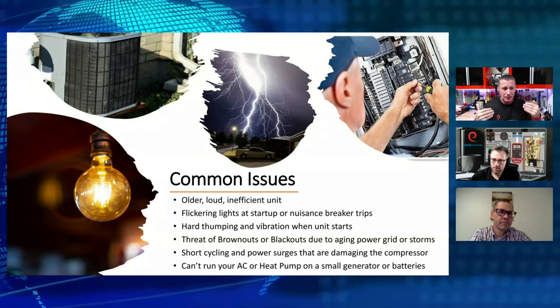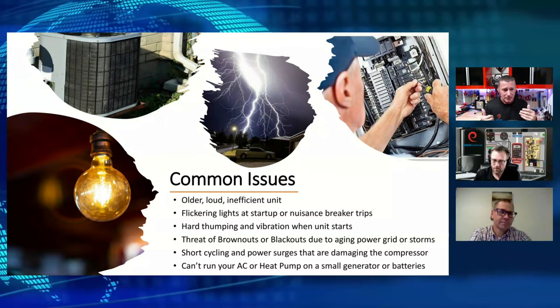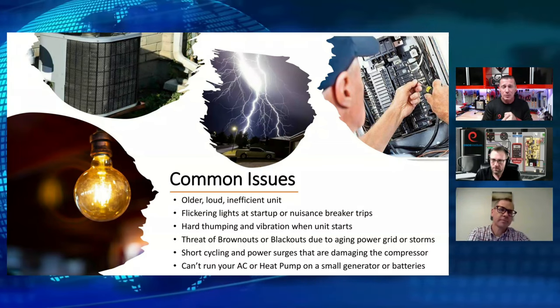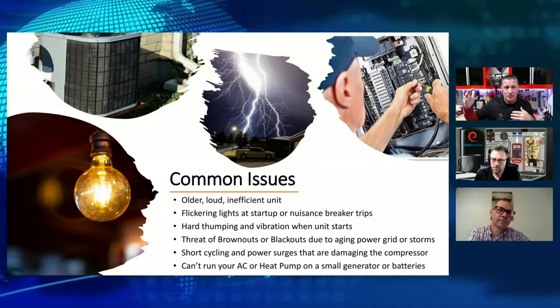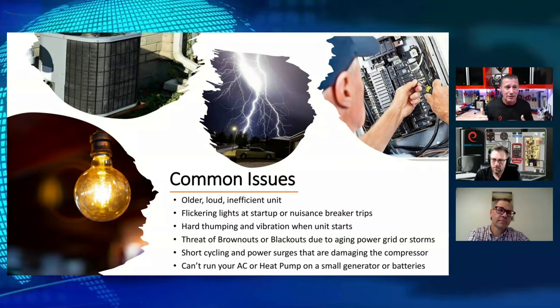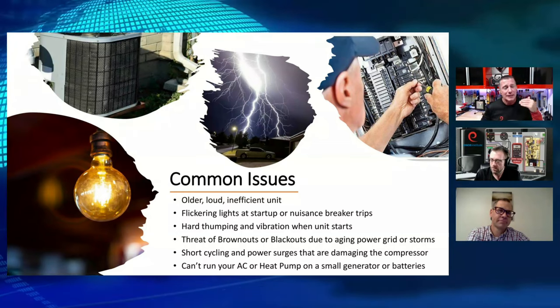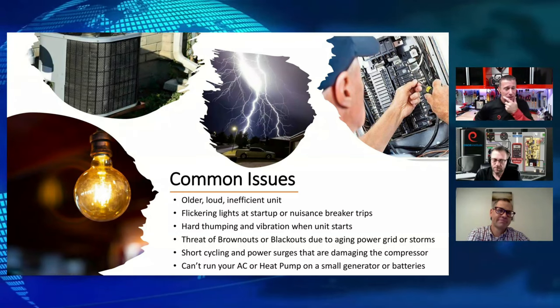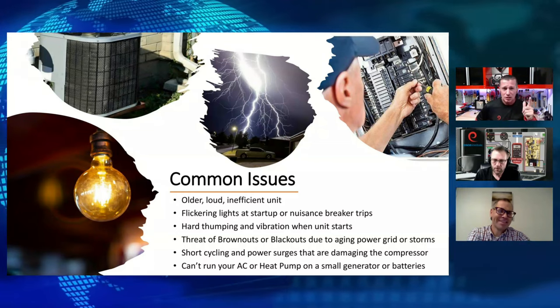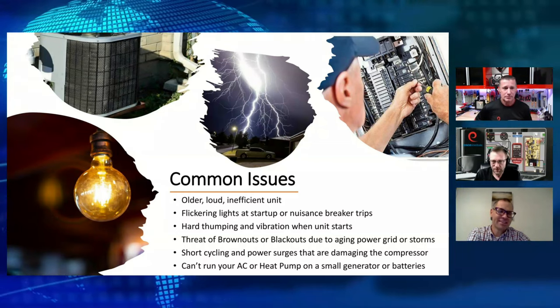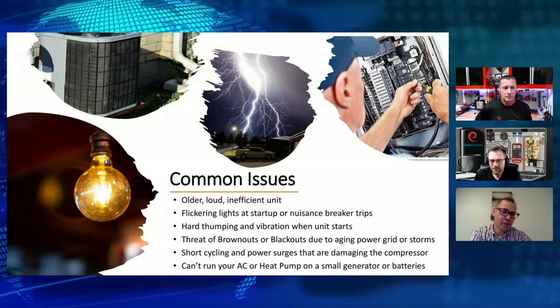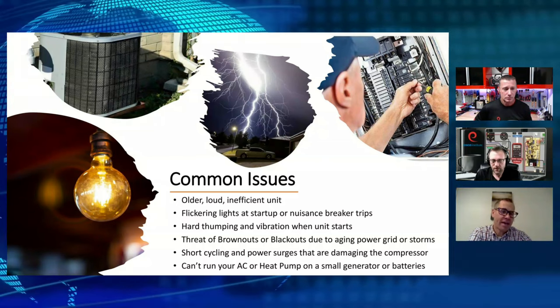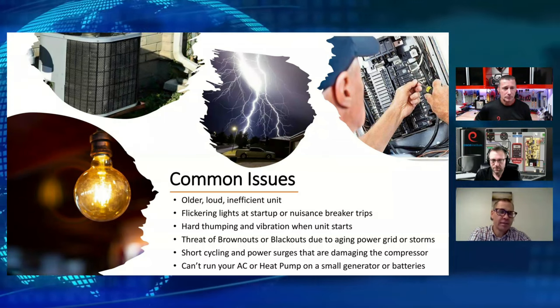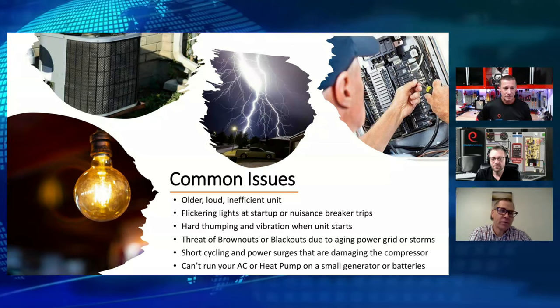They're on steady load ratings, right? Correct. So now we have to make sure that if we were sizing a generator for an air conditioner, we can't size that for 8.75 amps, we have to be able to get the thing up and running. So it makes a huge change. That's been the issue. So you need a much larger generator than in the past to run your air conditioner or heat pump if you wanted to do that.